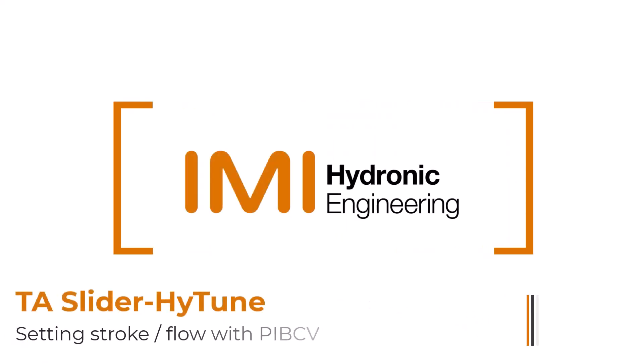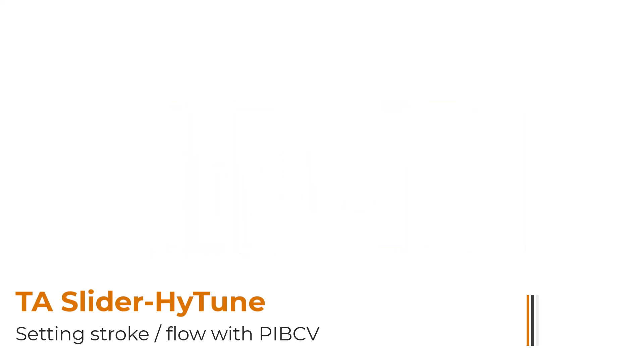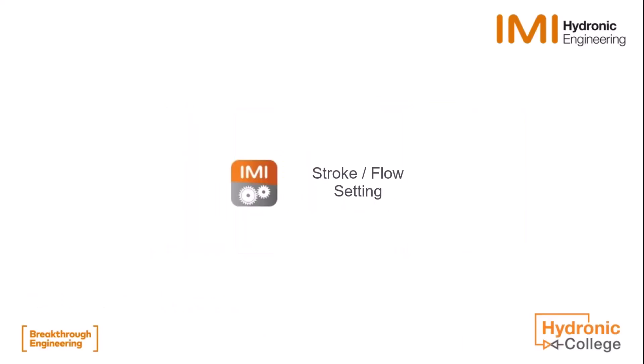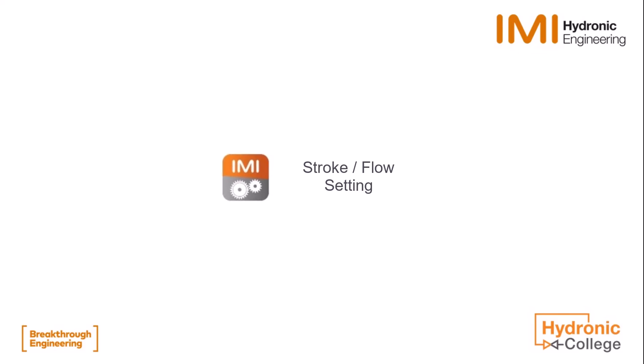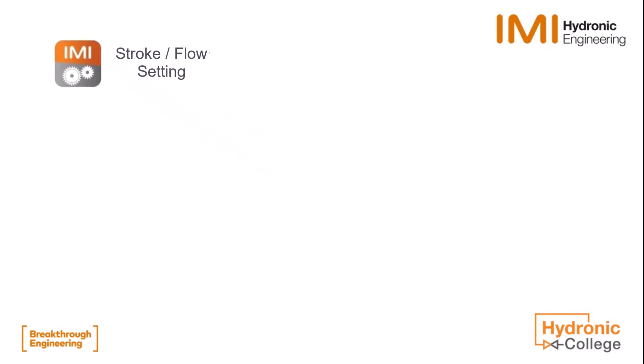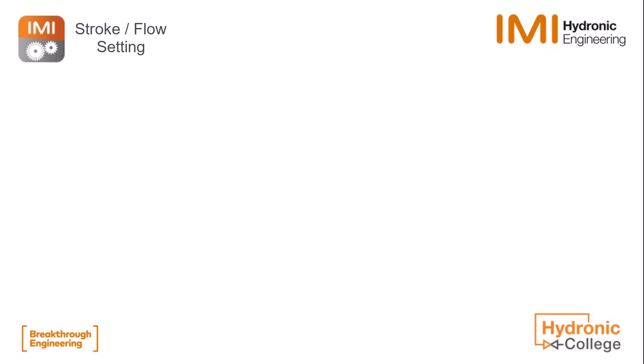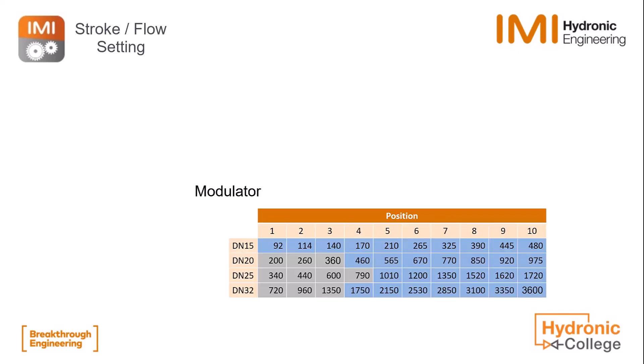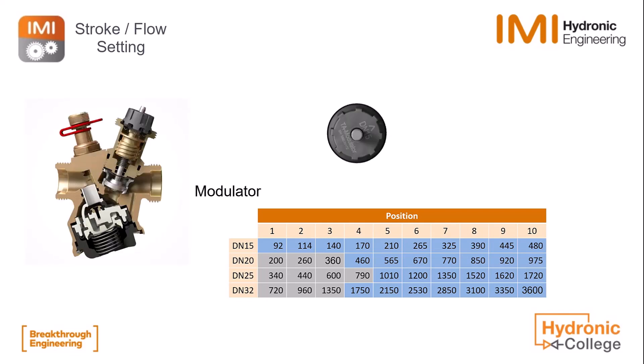Here we will talk about the possibilities when setting a combination slider with PI-BCV, like TA Modulator or TA Compact. A big advantage of using PI-BCV is that we know at which setting which flow will be limited by the valve. Since the TA Slider has all valve settings and flows in its memory, we now have the possibility to set the actuator to limit on flow instead of on stroke only. An additional option is that you can communicate this information via the bus when using a bus actuator.